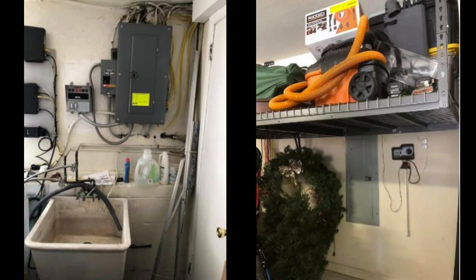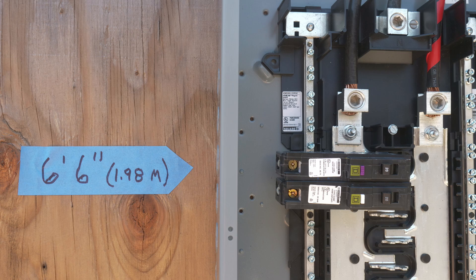So the photograph on the left clearly shows that the path to the panel is blocked, and on the example on the right there's not enough headroom. You need 6 and a half feet of headroom to get to the panel, and the fake Christmas tree should not be stored there.